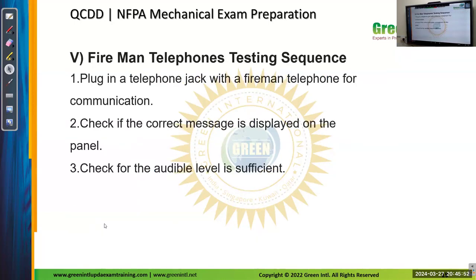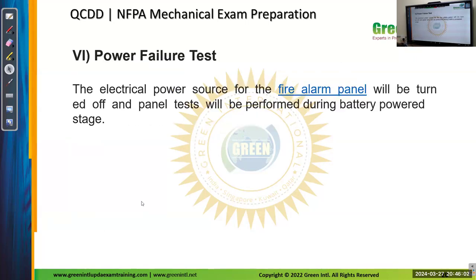Fireman telephones testing sequence. Plug the telephone jack in with the fireman telephone for communication. Check if the correct message is displayed on the panel. Check that the audible level is sufficient. So we are checking the devices. Power failure test. The electrical power source for the fire alarm will be turned off and the panel test will be performed during the battery powered stage.